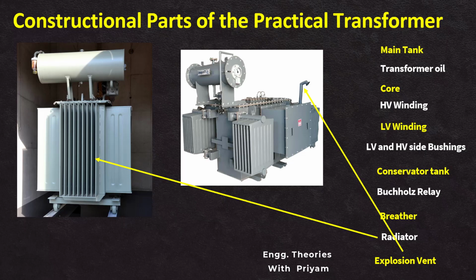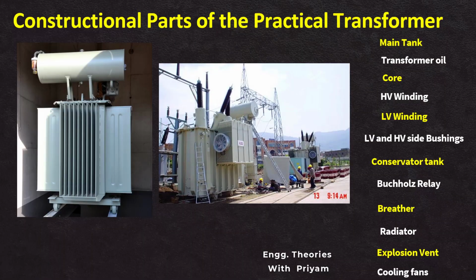A diaphragm fitted at the curved end breaks at a relatively low pressure to release the forces within the transformer. The electric fans in the transformer are commonly located within the cooling system to regulate and maintain optimal operating temperatures, typically positioned near the radiator or cooling fins. These fans play a vital role in dissipating the heat generated during the transformer's operation.